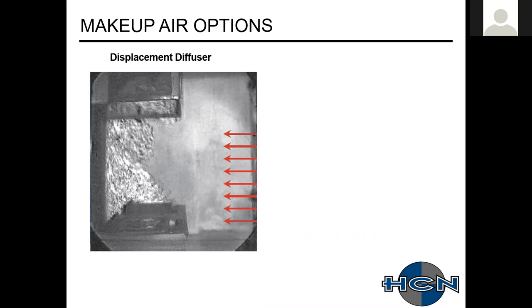However, typically with most diffusers, like floor or displacement diffusers, they usually go on the floor and the wall. There's not a ton of space in most kitchens. They're using that all up, so you can't really have them behind shelving, that kind of stuff. So it's a very effective strategy, but typically for most restaurants, they don't have space for that.